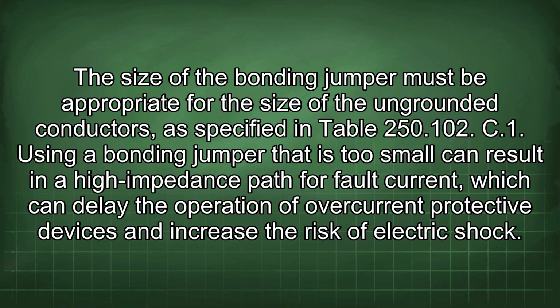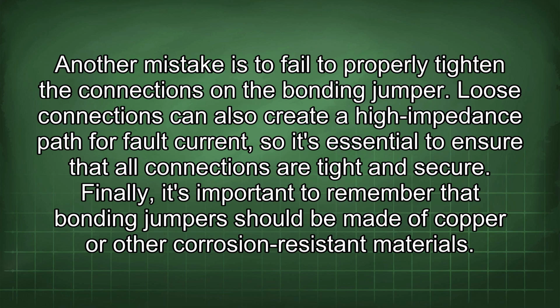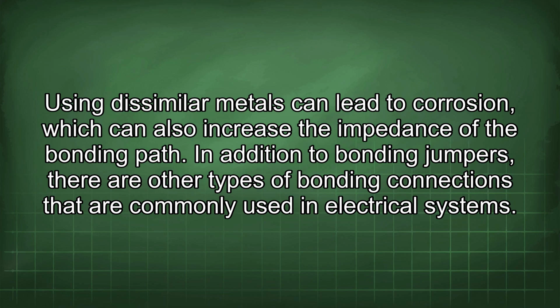250.102.C.1. Using a bonding jumper that is too small can result in a high impedance path for fault current, which can delay the operation of overcurrent protective devices and increase the risk of electric shock. Another mistake is to fail to properly tighten the connections on the bonding jumper. Loose connections can also create a high impedance path for fault current, so it's essential to ensure that all connections are tight and secure. Finally, it's important to remember that bonding jumpers should be made of copper or other corrosion-resistant materials. Using dissimilar metals can lead to corrosion, which can also increase the impedance of the bonding path.